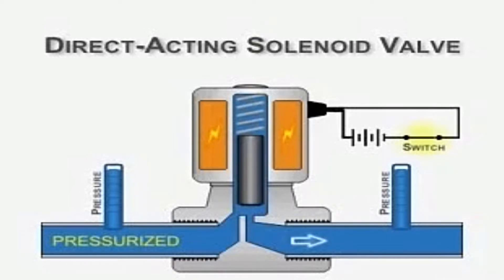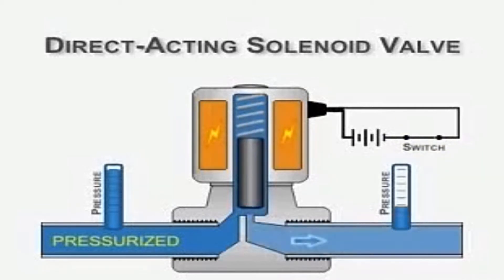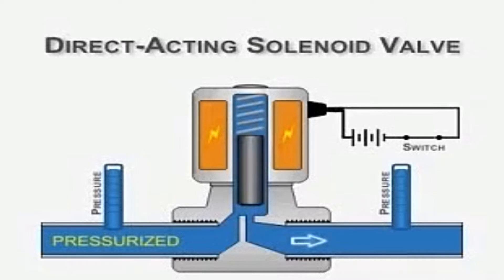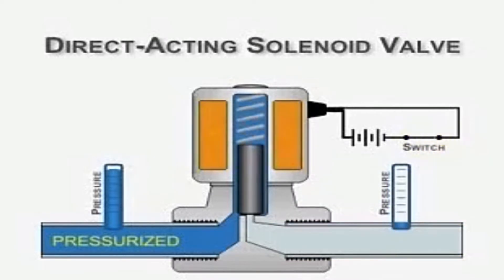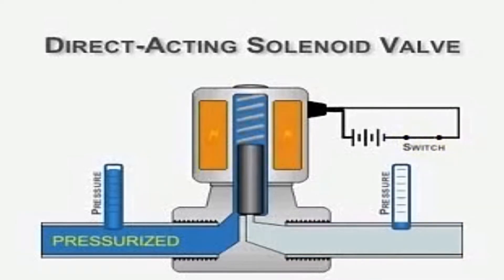When the coil is energized, it lifts the spring upward, which in turn lifts the plunger — similar to a plug and seat arrangement. The pressurized fluid from the upstream inlet port then flows into the downstream outlet port, pressurizing the downstream application. This is how a direct-acting solenoid valve works.